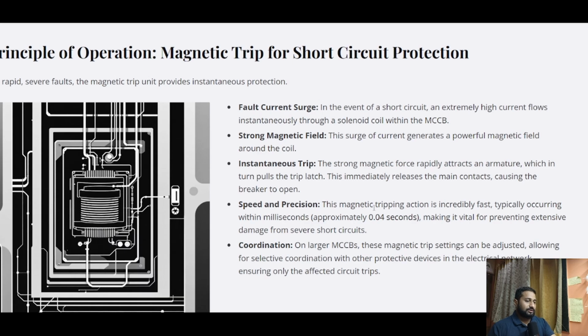Speed and precision. This magnetic tripping action is incredibly fast, typically occurring within milliseconds, approximately 0.04 seconds, making it vital for preventing extensive damage from severe short circuits. Then the coordination on large MCCBs. These magnetic trip settings can be adjusted, allowing for selective coordination with other protective devices in an electrical network, ensuring only the affected circuit trips.